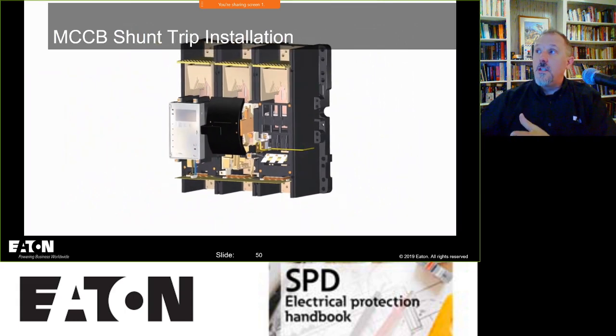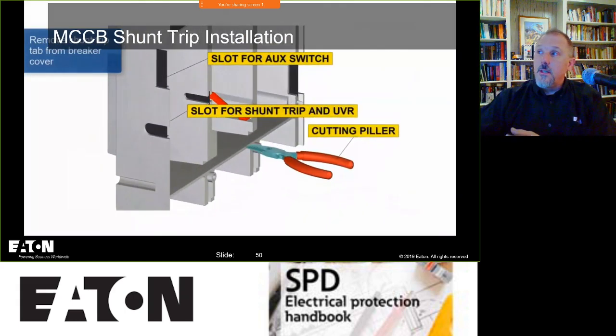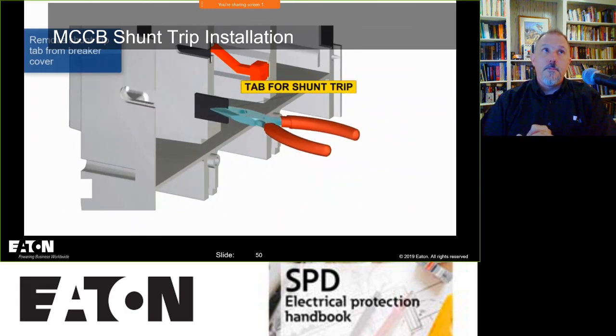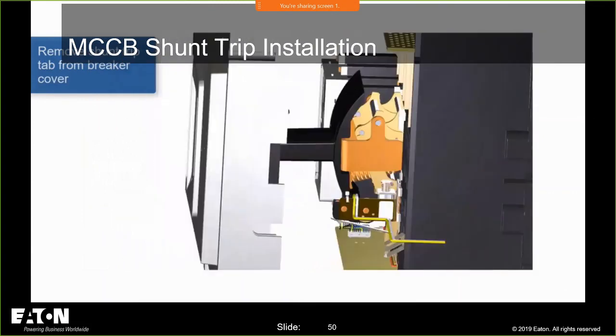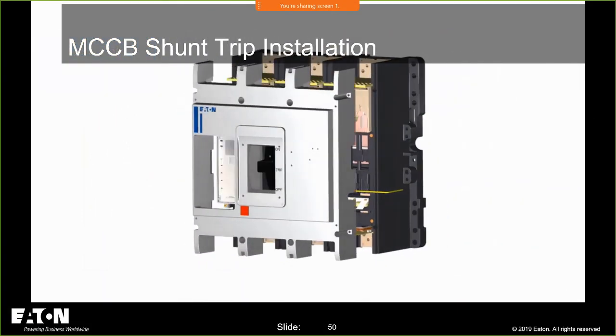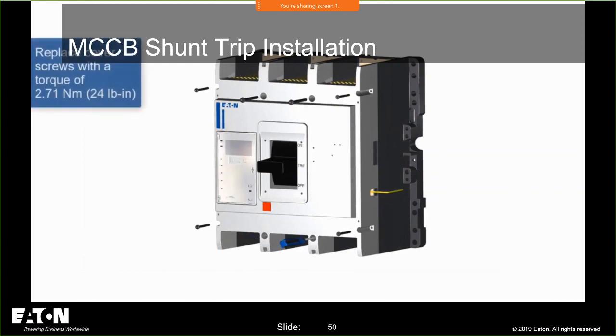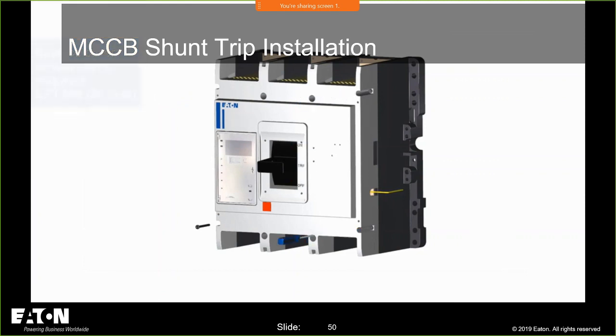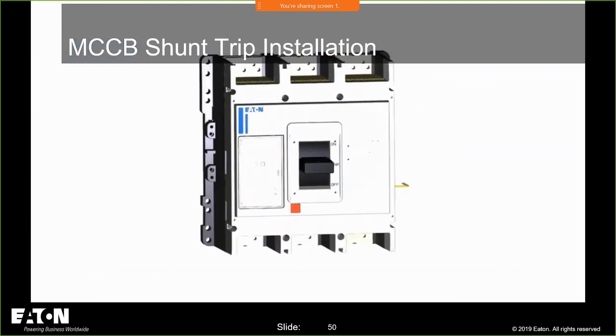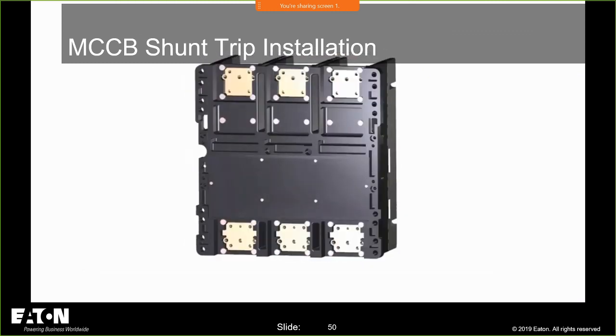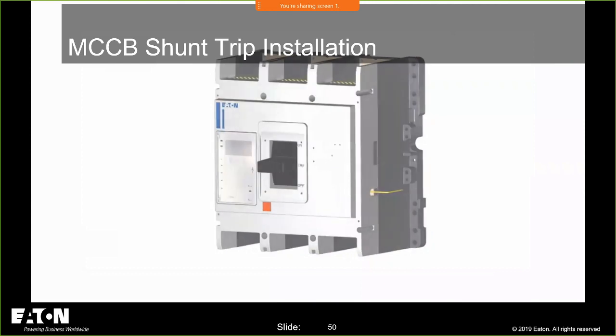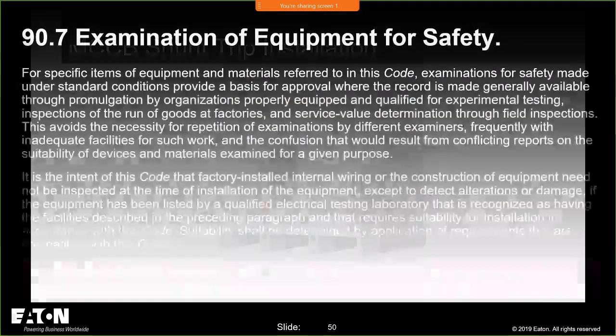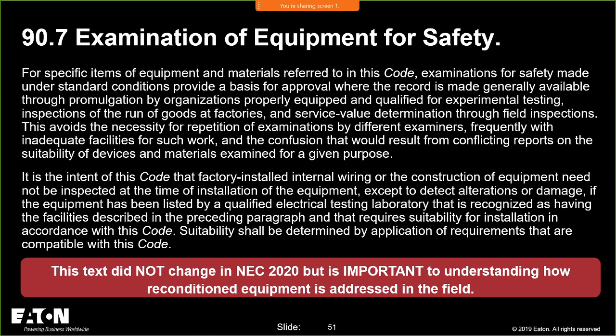There are specific provisions, like I said, the screws are one. There are slots on the side that tell you how to take that in and out and how to take the wires out the side. They tell you what the torque requirements and specifications are. There's no seal on the side of these breakers because we anticipate that at some point you're going to be replacing those or adding accessories. So that's just one aspect of what would not be considered a modification because you're following manufacturer's instructions.